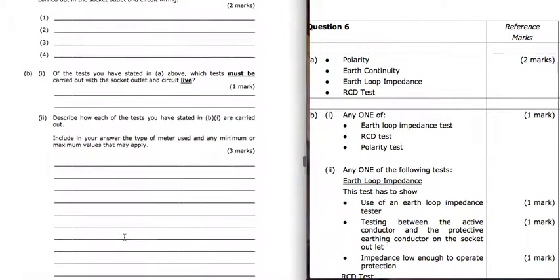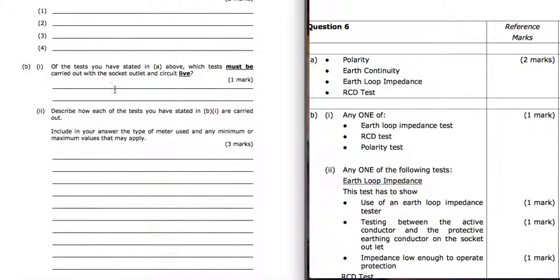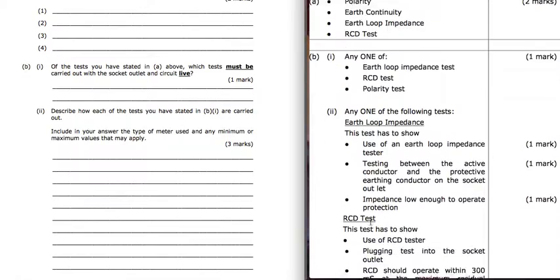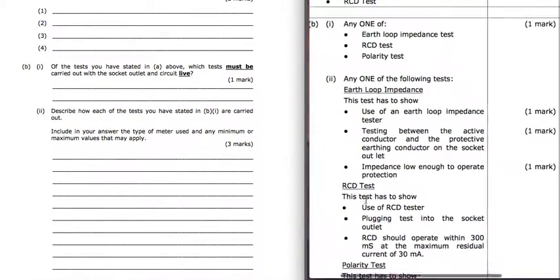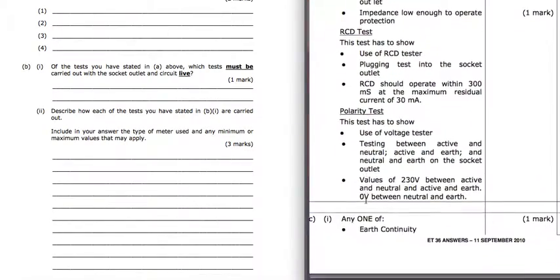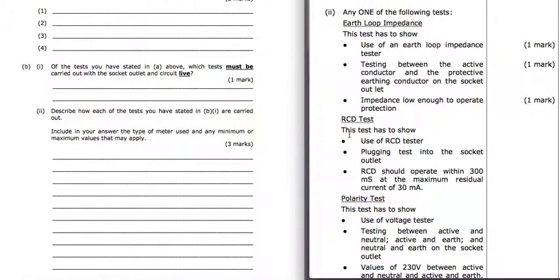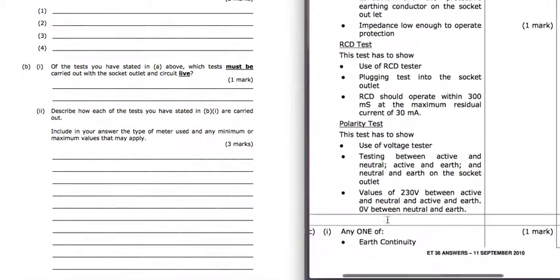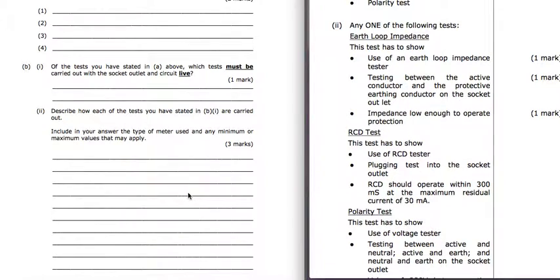And then what they're asking you to do here is, for the one that you've said there, answer this question about type of meter, maximum and minimum values that apply. So they've gone through each of the ones there: earth loop impedance, RCD, polarity. I would be answering the RCD one if this was me. Much easier. Use the RCD tester, plug it in, make sure it operates within that 300 milliseconds with a maximum of 30 milliamps. But you can describe any of those tests.